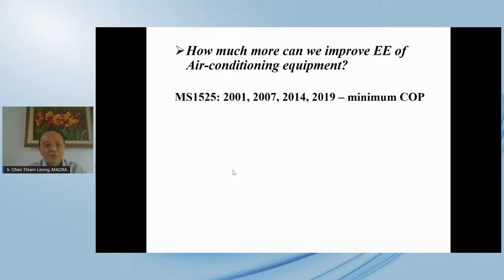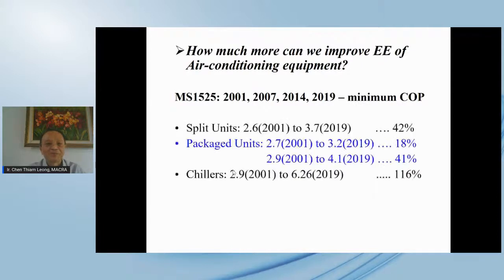For those unfamiliar, COP, coefficient of performance, is basically the energy efficiency of the air conditioning equipment. Progressing from 2001 to 2019, you can see that for split units, the Malaysian standard stipulated a COP of 2.6 in 2001. The higher the COP, the more efficient it is. By 2019, we improved it to a minimum of 3.7, a 42% improvement. So the industry has been working very hard on this.